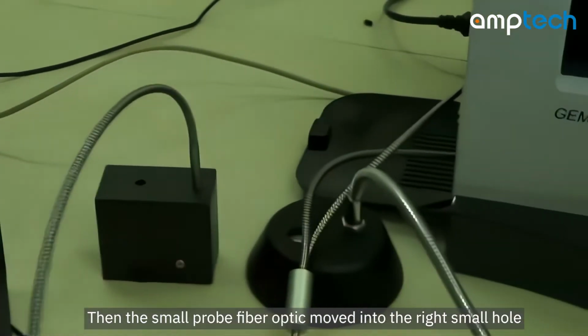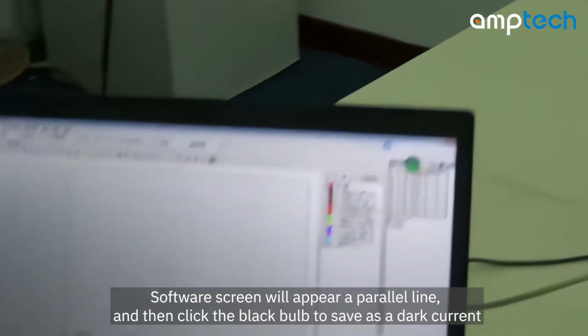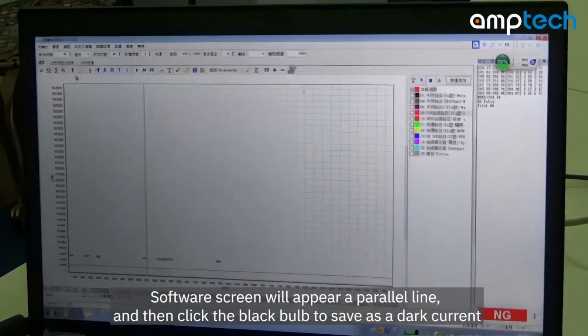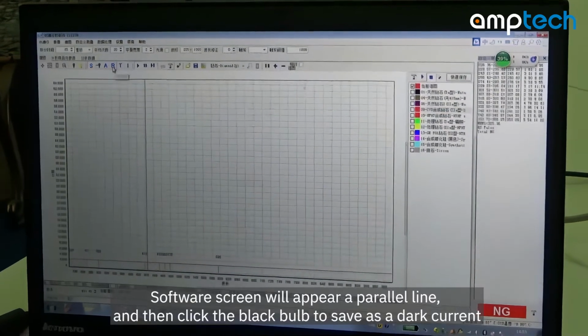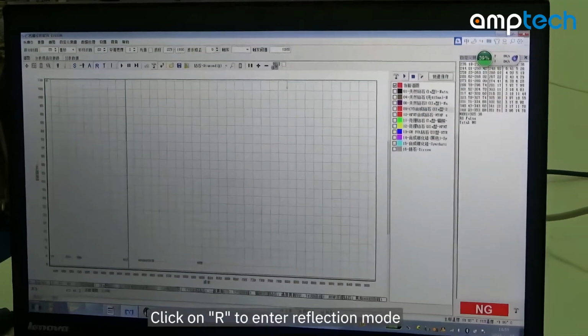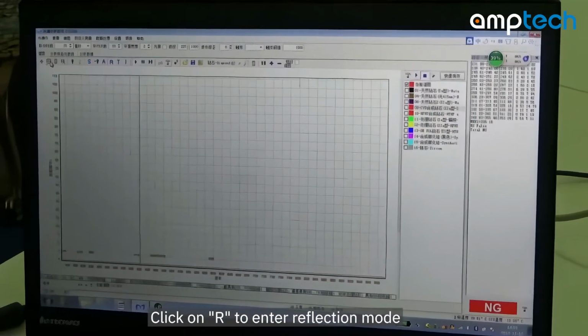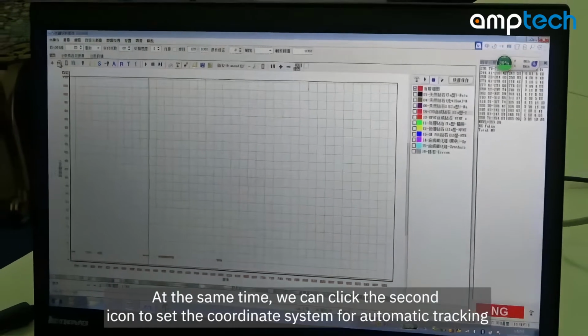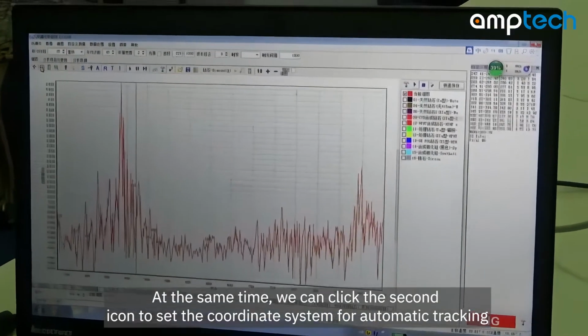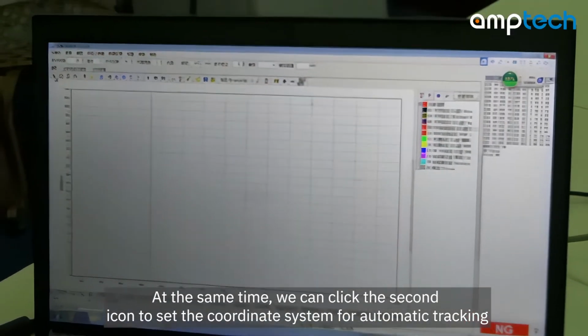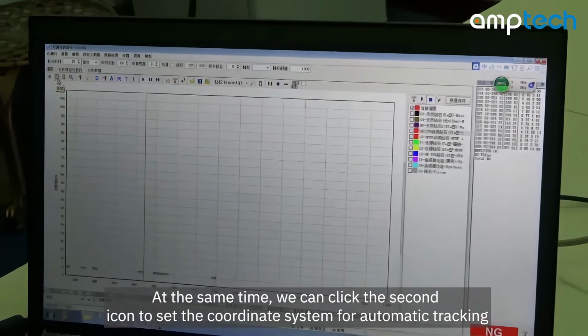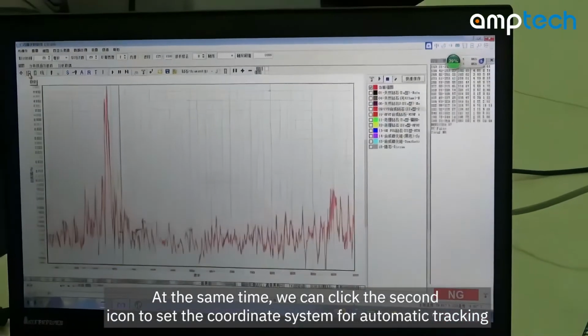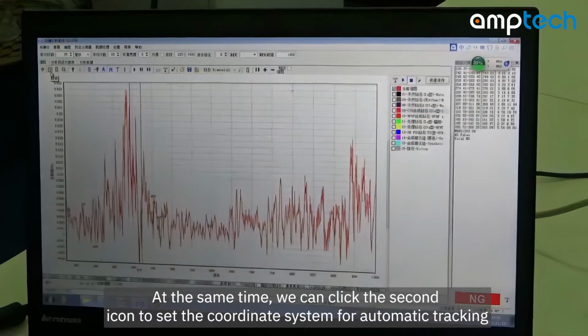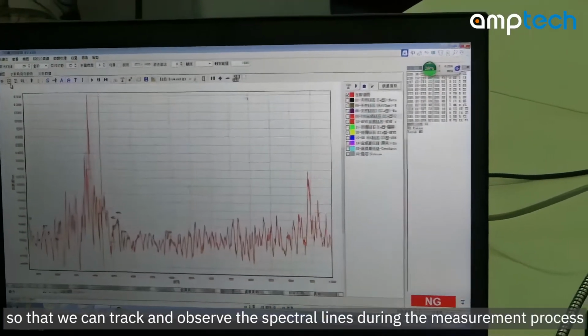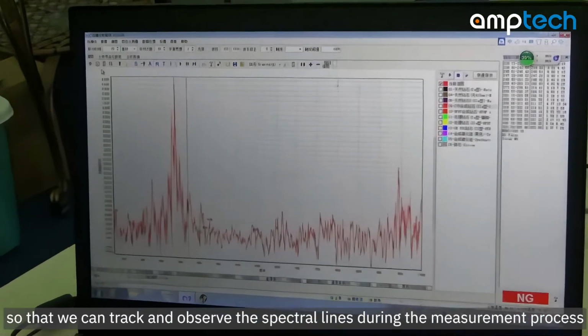Then move the small probe fiber optic into the right small hole. The software screen will show a parallel line, and then click the black bulb to save as a dark current. Click on R to enter reflection mode. At the same time, we can click the second icon to set the coordinate system for automatic tracking, so that we can track and observe the spectral lines during the measurement process.